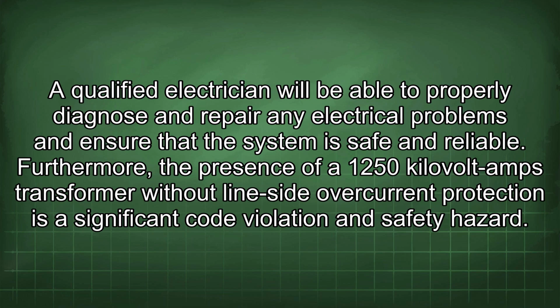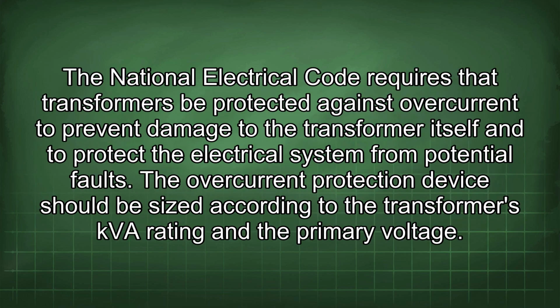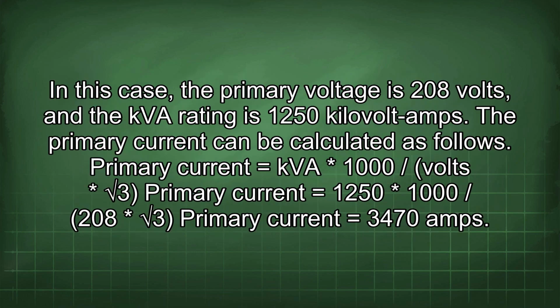A qualified electrician will be able to properly diagnose and repair any electrical problems and ensure that the system is safe and reliable. Furthermore, the presence of a 1250 kVA transformer without line-side overcurrent protection is a significant code violation and safety hazard. The National Electrical Code requires that transformers be protected against overcurrent to prevent damage to the transformer itself and to protect the electrical system from potential faults. The overcurrent protection device should be sized according to the transformer's kVA rating and the primary voltage. In this case, the primary voltage is 208 volts and the kVA rating is 1250 kVA.